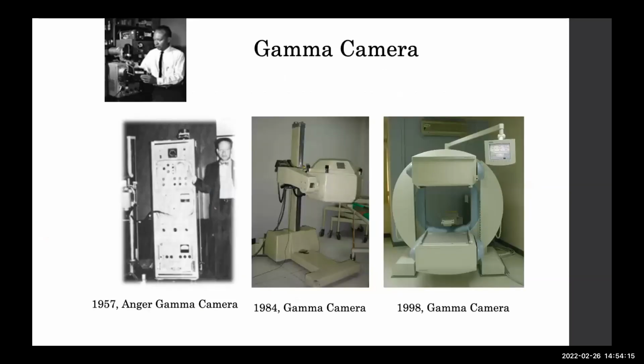Now we come to a very basic instrument which every nuclear medicine department has, the gamma camera. The gamma camera was designed by Anger in 1957. This is the basic prototype Anger gamma camera. This is a very simple gamma camera from the 1980s, where it has only the detector assembly and a stand where the detector can move up and down. That's all. There is only one way of movement, and this is a trolley on which the patient used to lie, and that trolley used to be brought under the camera, and simple planar imaging used to be done. In the early 80s, we used to have this type of camera. Then came the dual head detector cameras, which have the capability of rotating around the patient. So in the 90s, we started having SPECT cameras. Initially, we used gamma cameras in the 80s.